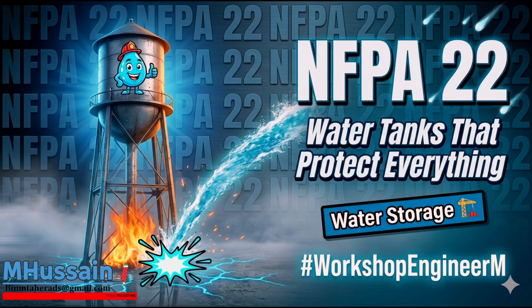Yeah. If we look at the math, standard atmospheric pressure at sea level is roughly 14.7 pounds per square inch. Correct. If you have a perfect absolute vacuum, that 14.7 psi can theoretically support a column of water approximately 33.9 feet high. That is the theoretical maximum. But fire pumps are not perfect vacuums, and real-world fluid dynamics introduce massive penalties. Like what? Well, you have severe friction losses as the water moves up the hard suction hose. You have mechanical efficiency losses in the pump casing.